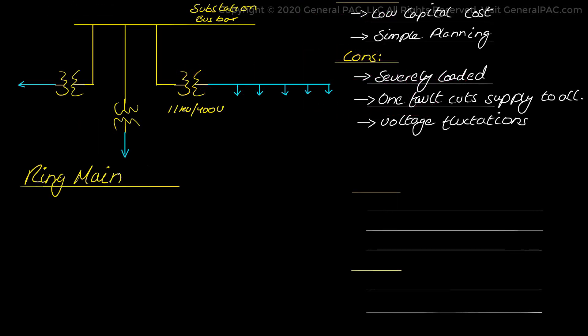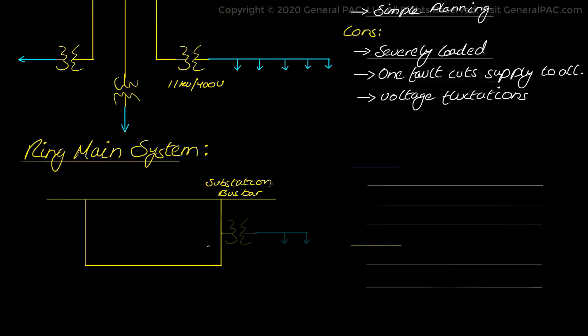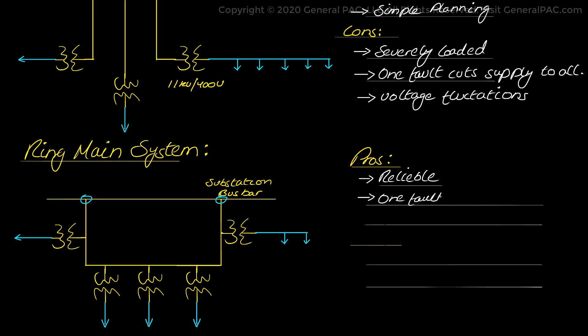Secondly, we have the ring main system. In this type of system, the primary side of the distribution transformers are linked to form a loop. The loop circuit starts from the substation bus bars, makes a loop through the area to be served, and returns to the substation. Therefore, it consists of at least two paths between the substation and the consumer. The ring main system is very reliable as each distributor is fed by two feeders, and if a fault occurs at any single point in the feeder, the continuity of supply will be maintained. Consumers also face fewer voltage fluctuations due to the injection of current from both points.